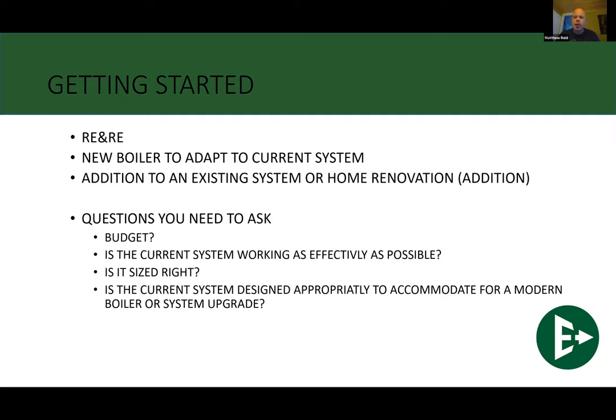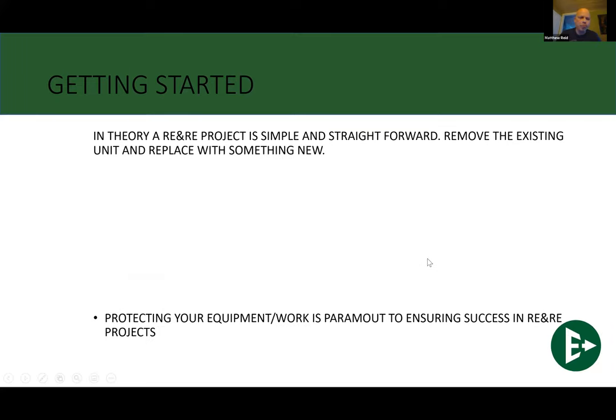And is the current system designed appropriately to accommodate a modern boiler system upgrade? What that means is, if you're changing maybe a gravity system, and it's got the big 3 or 4 inch pipes in there, you can't really oversize pipes, so you're going to be fine with that. But do we need to put a couple pumps in? Do we have room for the condensate pumps? Because these new systems are going to be condensing. Most of the time, not a lot of people go with the old style common vent system. So just some points to keep in mind as you're figuring it all out.